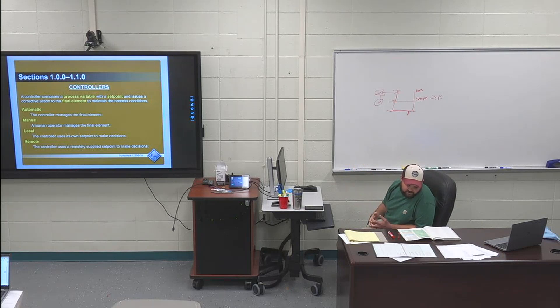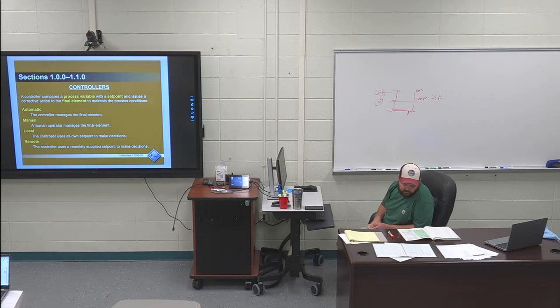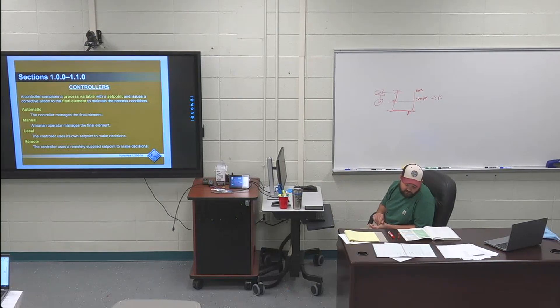The rest of that is a separate highlight. Note: do not confuse local control with manual control. Manual control affects the output of the controller, while local control affects where and how the controller gets its set point.